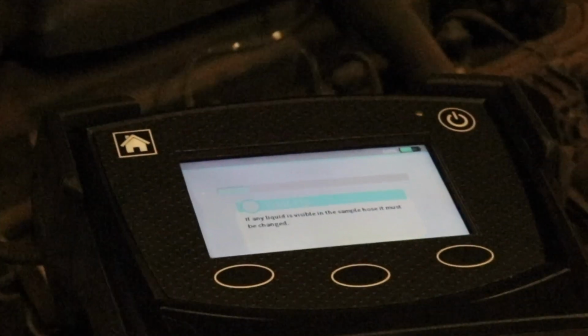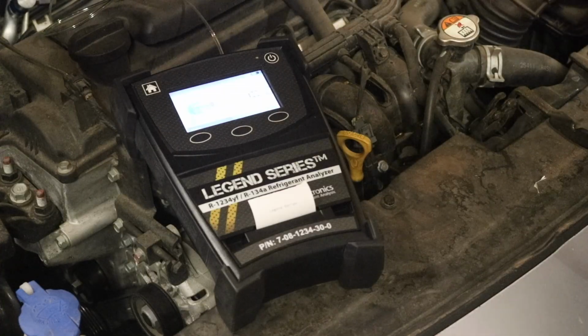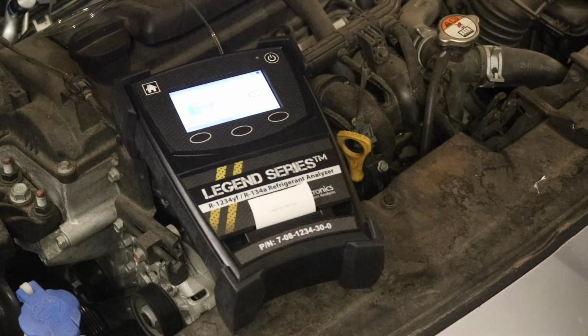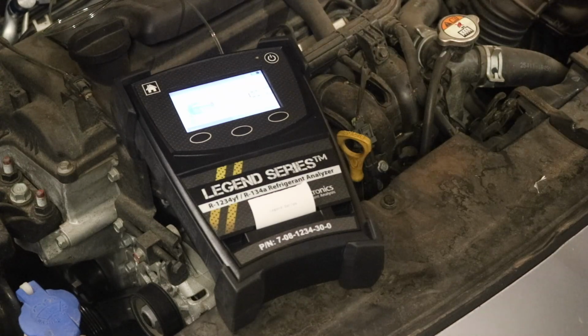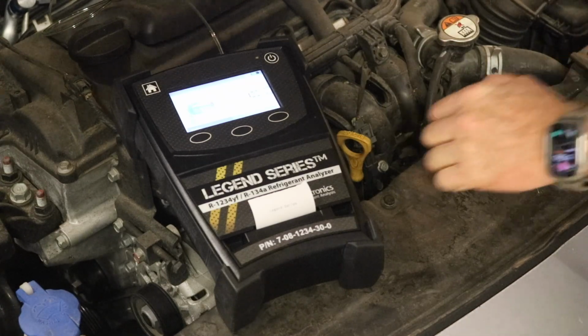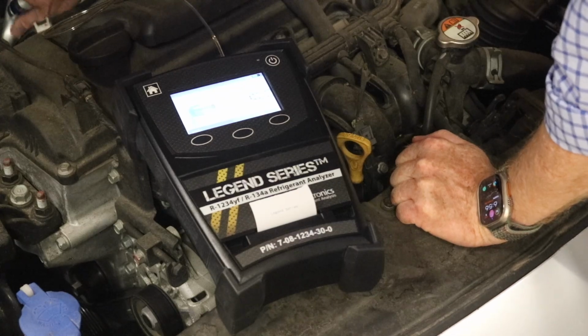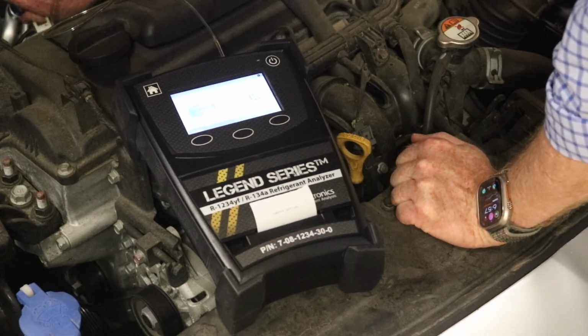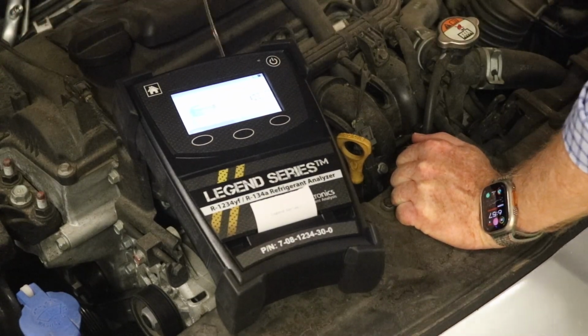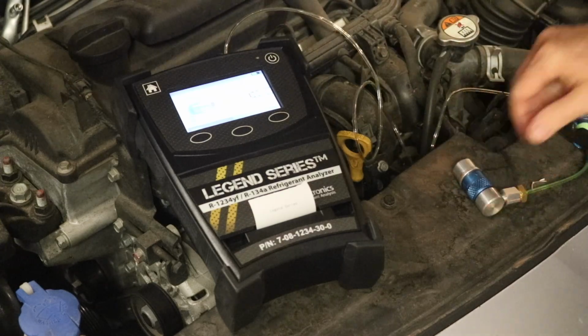And again, this process takes a little less than 30 seconds for it to do its job. You get the progress bar and it indicates on the screen that the test is taking place. Okay, the testing process has just completed. We heard the 3 beeps, and we're now giving instructions to disconnect from the source. So I will wind out my coupler from the low side access port and disconnect from the source.